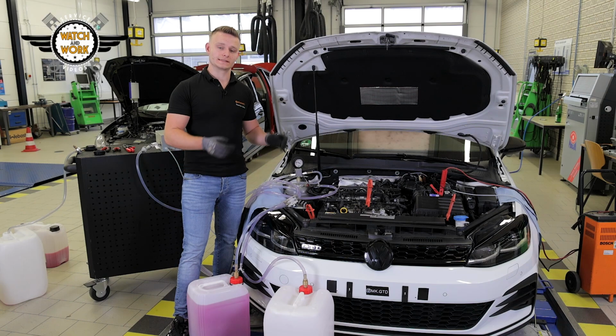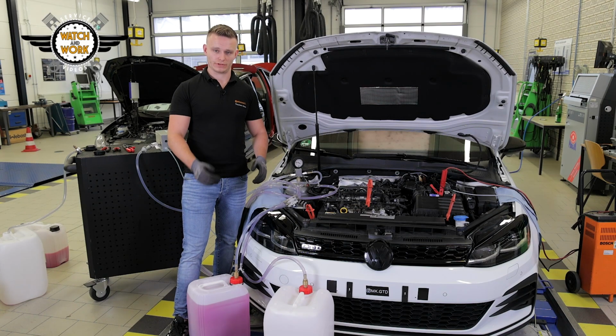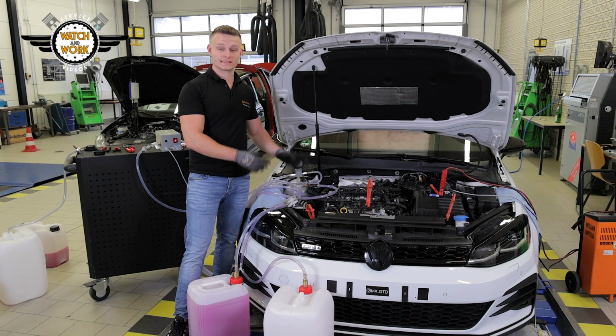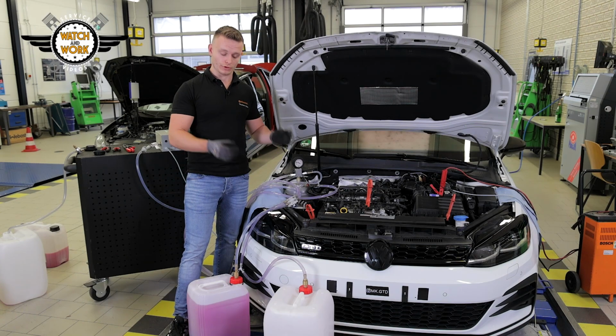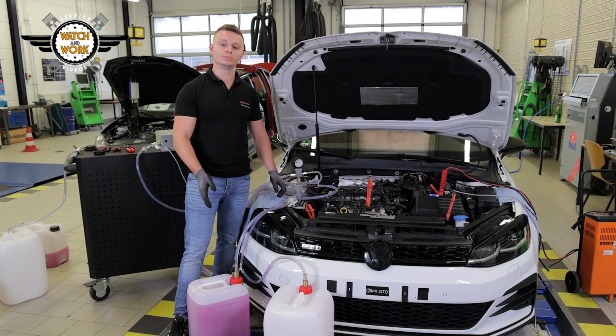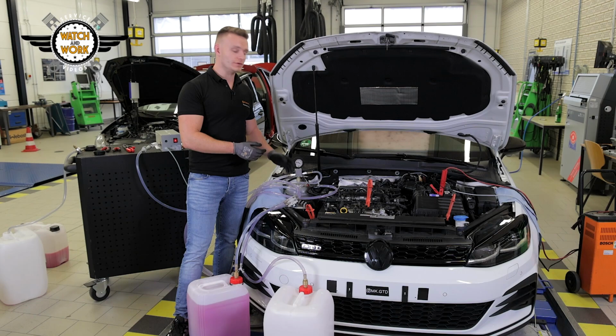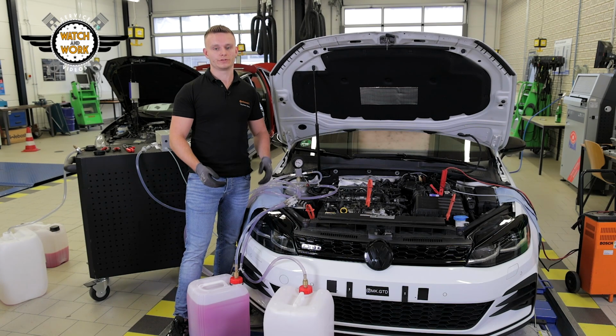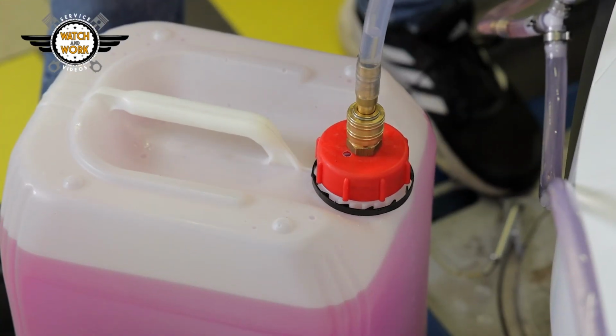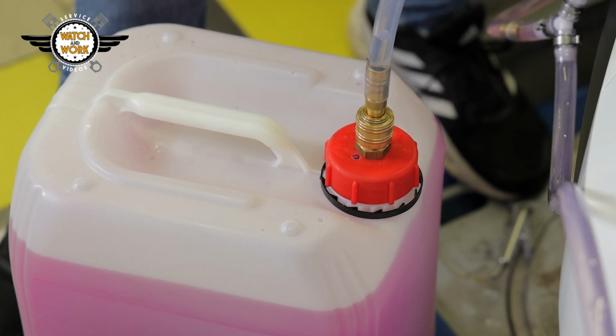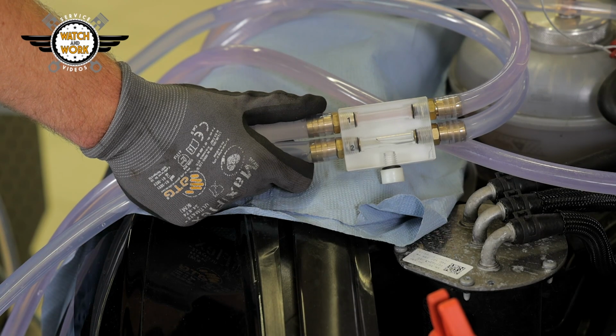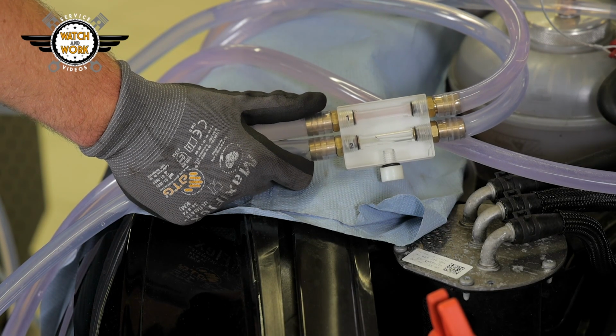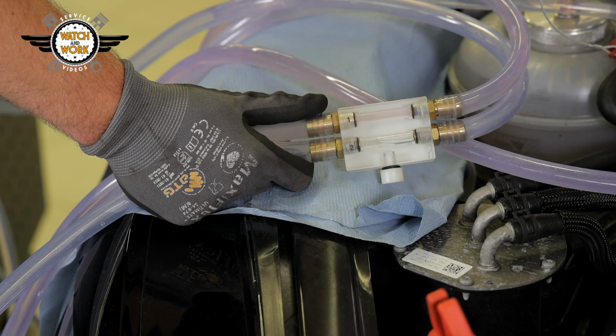So we've removed the used coolant from our cooling system, but the whole system is now filled with distilled water. We want to fill it with fresh coolant. This is done by once again carrying out each of the flushing processes using coolant this time. We've now swapped the distilled water for coolant. We keep flushing until the coolant color is clearly noticeable in inspection glass 1.